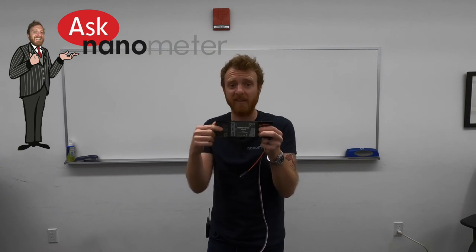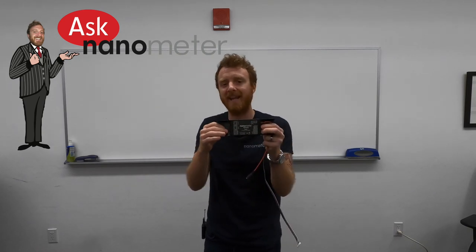At Nanometer we have our DM10X dimming interface and this device is designed to the dimming ballast standard but with an added bonus. You see the DM10X sources the power as expected, but the electrical components are designed to allow the current sourcing controller to override the device's authority. Effectively it means it will auto switch between sink and source in the field as required.